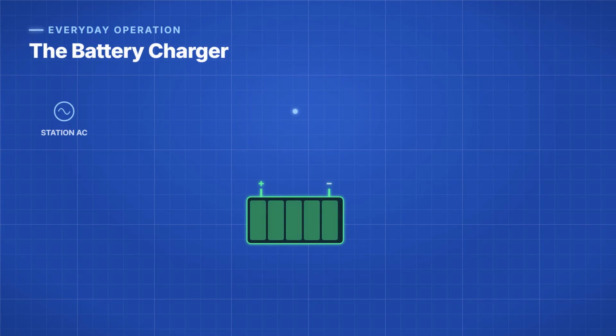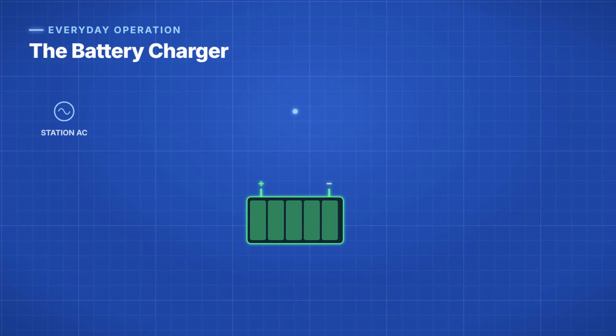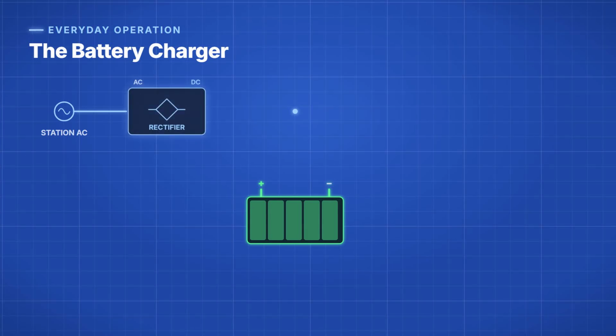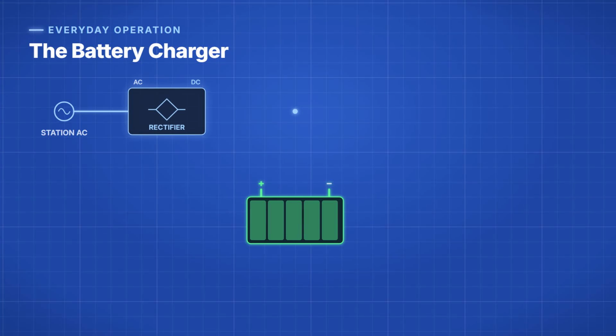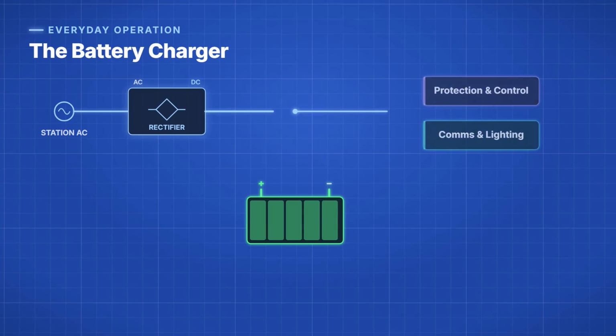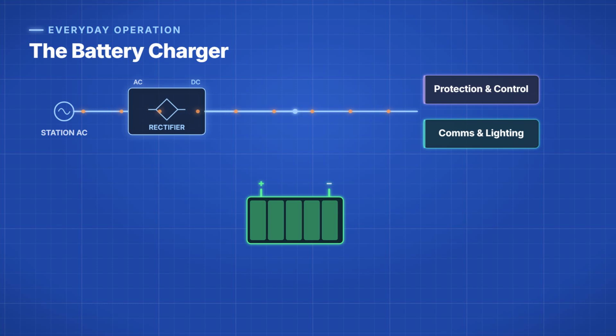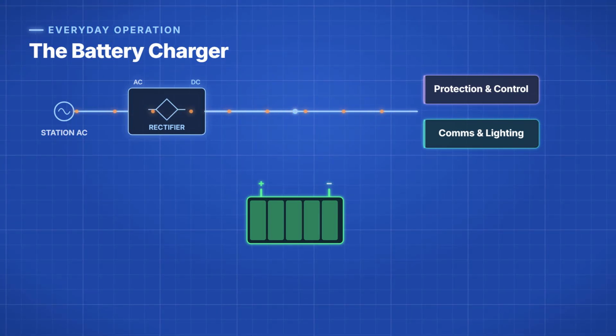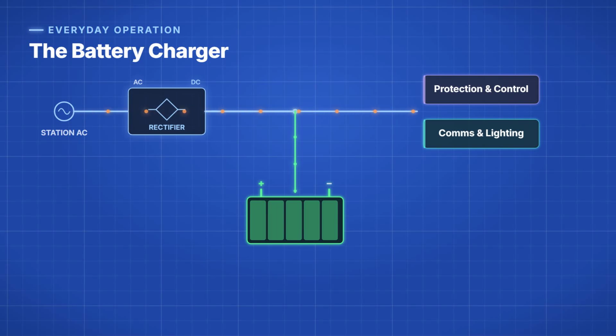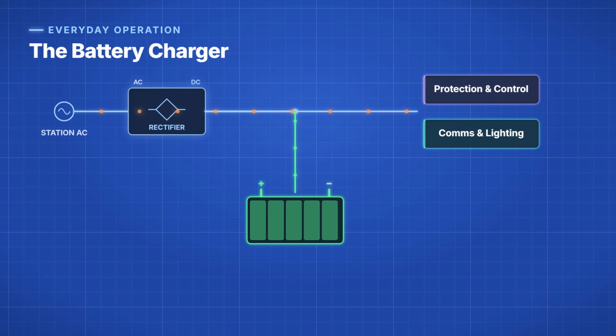Here's a question that catches people out. If the battery is so important, what's powering the substation's DC loads day to day? The answer is the battery charger, which is really a rectifier. That's a device that takes the station's alternating current supply and converts it into smooth DC. And the charger does two jobs at once. It feeds all the DC loads directly, and at the same time, it keeps the battery topped up. Holding the battery at a steady voltage so it stays full without overcharging is called float charging.